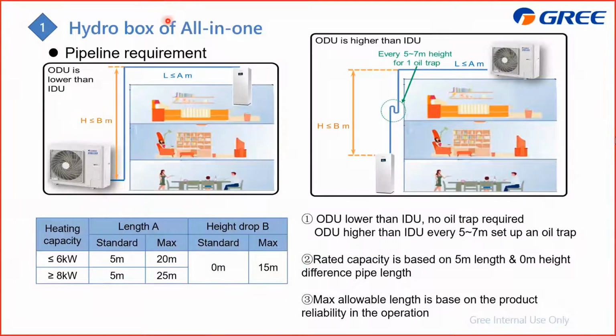And as for the split type, for this one, you can also find that if the outdoor unit is lower than the indoor unit, there's no oil trap requirement. And if the outdoor unit is higher, in that case also, at the same 5 to 7 meters, set an oil trap. And you also need to ensure the total pipeline length is within the range, otherwise the system reliability cannot be ensured.